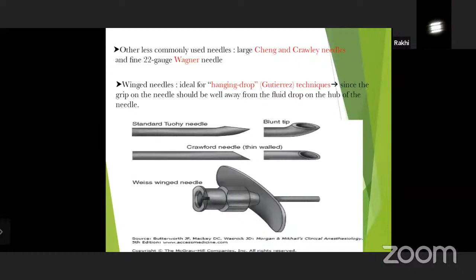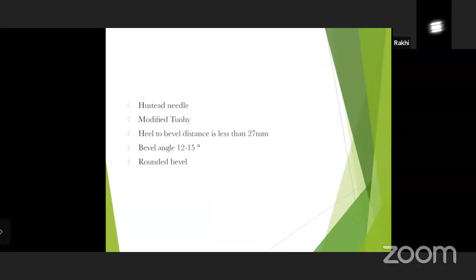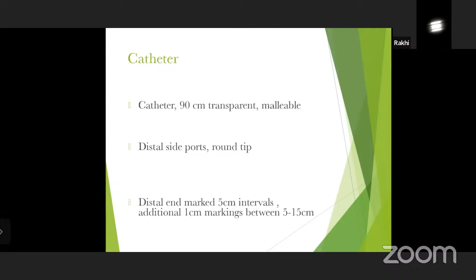The heel to bevel distance is less than 27 millimeter and the bevel angle is 12 to 15 degree. It has a rounded bevel which will avoid the catheter shearing at the tip of the needle. Then the epidural catheter. The epidural catheter is a 90 centimeter transparent, malleable, biologically inert catheter which is made up of nylon and Teflon. The distal end has a distal side port and a round tip. The distal end is marked at 5 centimeter intervals, with additional 1 centimeter markings between 5 to 15 centimeters.